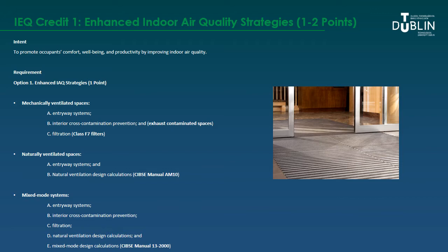For naturally ventilated spaces under option one, you need to meet the entryway system requirement and the natural ventilation design calculations from the CIBSE manual, which gives guidance on directing airflow in naturally ventilated buildings. For mixed mode systems, you need to meet the entryway system, interior cross-contamination prevention, filtration, natural ventilation design calculations, and a mixed mode design calculation demonstrating that occupied spaces comply with the CIBSE guidance for mixed mode systems.